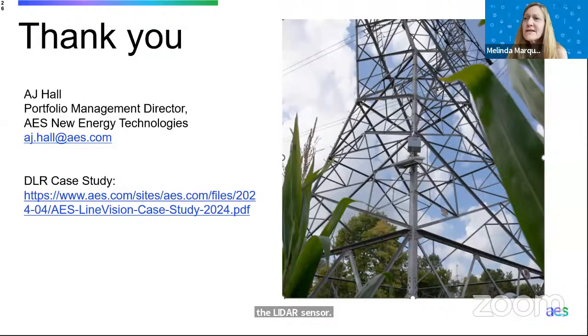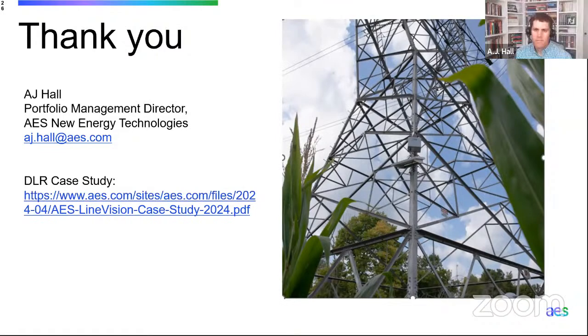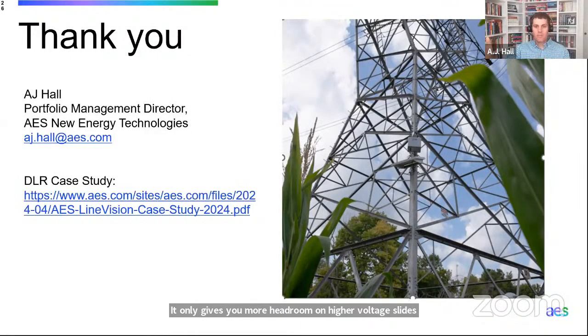Patrick also asks, what's the highest voltage at which you'd consider applying DLR? AES only operates 345 kV lines, and as I said earlier, DLR gives you more headroom on higher voltage lines—there's more to go after. I'd encourage system operators to look at larger 500 kV or 765 kV lines, since your bang for your buck from a deployment standpoint will be greatest when you consider megawatt per megawatt-mile of capacity gained.